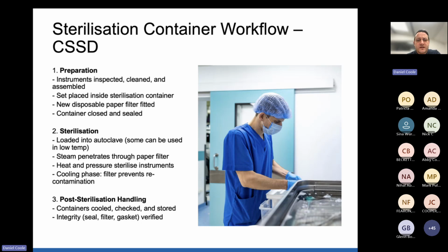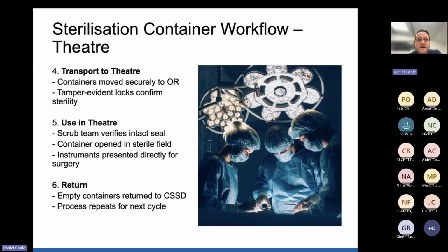Steam penetrates through the paper filter. Heat and pressure sterilise the instruments. And in the cooling phase, the filter prevents recontamination. So for post-sterilisation handling, containers cool, and they're checked and stored. Obviously, we want to make sure the integrity is there, so looking at things like the seal, the filter, the gasket, and verifying that. And then obviously transporting to theatres.